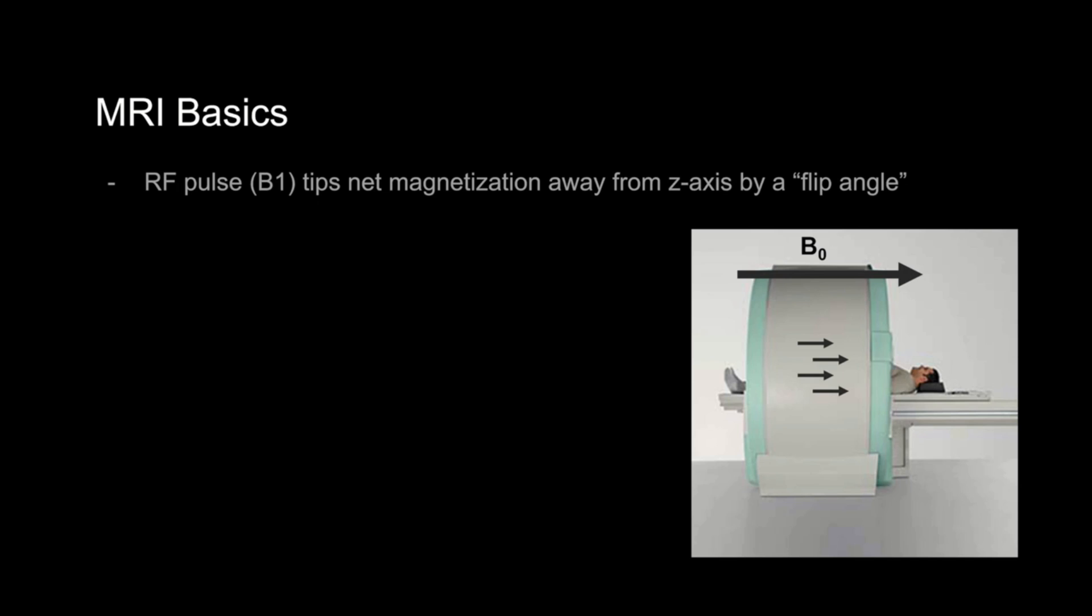A key point is that in order to tip the magnetization away from the z-axis, the RF pulse has to be at a frequency that matches the spin of what it's trying to tip down. For now, who cares about these details? What matters most is that the RF pulse tips the net magnetization away from the z-axis and into the xy plane. How much it tips away from the z-axis is called the flip angle. Here, for simplicity, let's say that this is 90 degrees for now, and again, with this 90 degree RF pulse shown here with B1, the net magnetization is tipped into the xy plane, again perpendicular to the z-axis that we described prior.